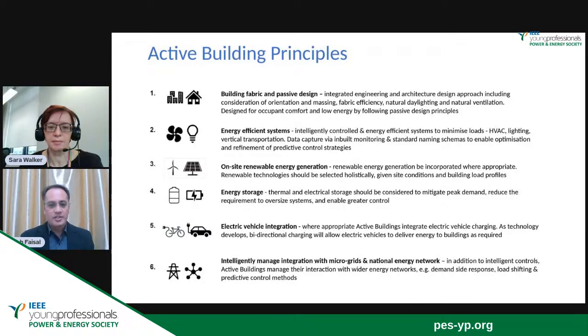Okay, I can ask one question regarding the virtual power plant and integration of this building with the national grid for cost optimization purposes. Yeah, so our local substation is 11 to 33 kV. It's connected to the Northern Power Grid distribution network. At the moment, the way in which demand response works in the UK system is that it is purchased by National Grid, and you have to be a fairly large load to offer demand response, or a very large battery. And so in the UK at the moment, given the size of the building, we can't currently bid into demand response markets on our own.